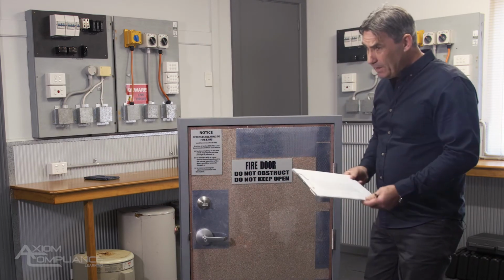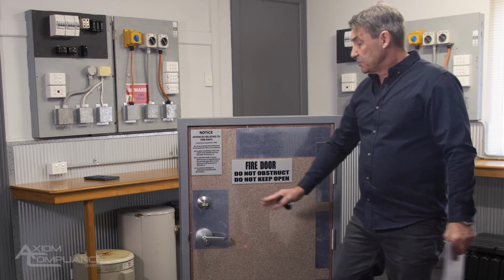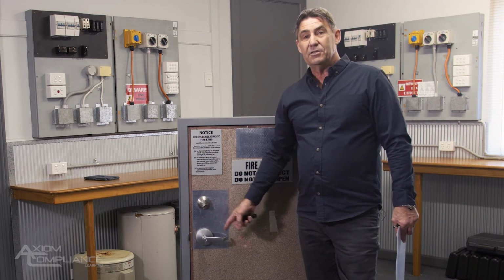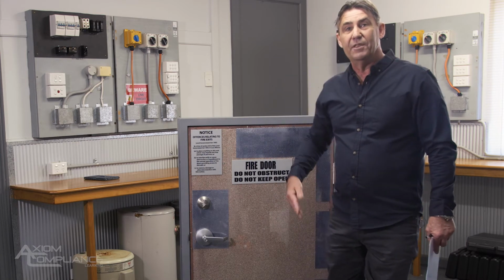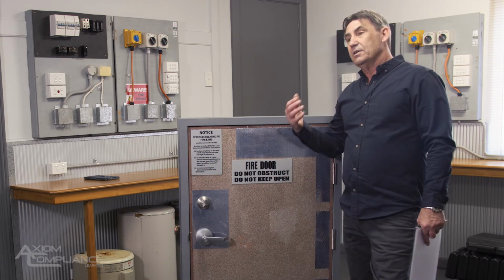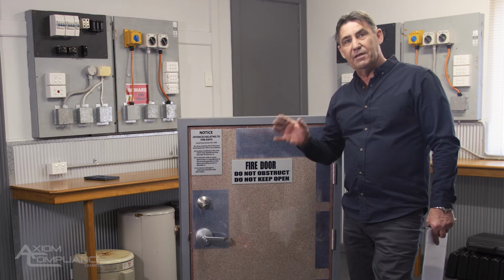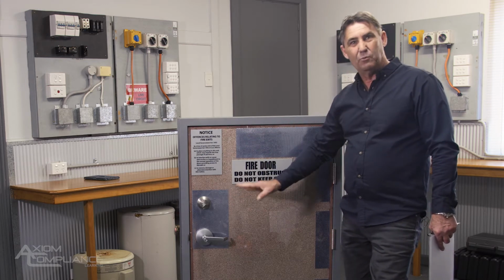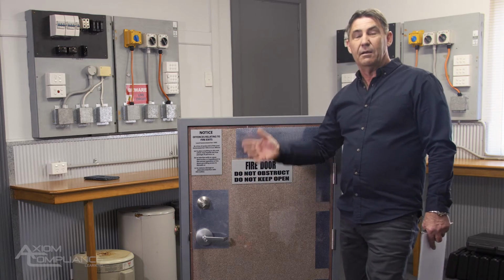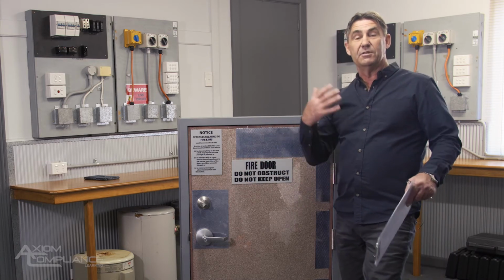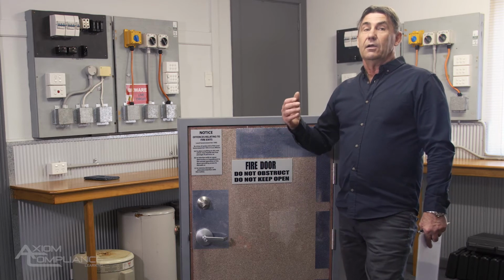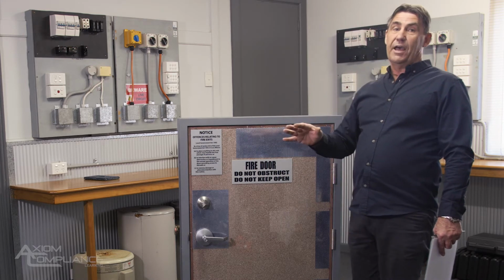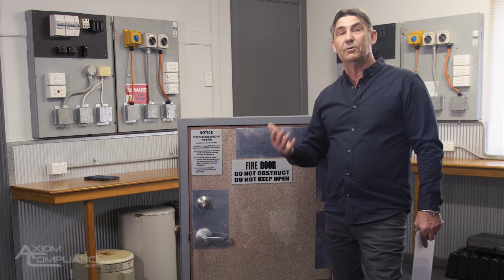Hardware. We've got to check and make sure that the hardware used on the door is the type that was on the door when the testing took place. As somebody who sponsors a test on a door, a manufacturer has to send this away to be burnt. And all of the hardware and the different types of hardware must be tested with the door, and that becomes a door set. So when you're doing these doors, this is the hardest part. We really should have a door register in the building.